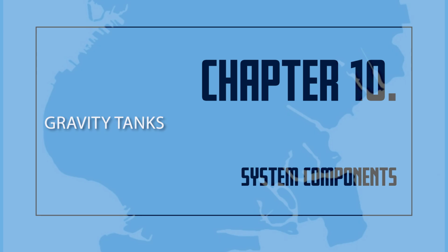Tanks may be located on the tops of buildings or raised on tall supporting towers. The water pressure in a gravity tank system depends on the elevation of the tank. This is the main advantage over other kinds of systems. For every 1 foot the tank is above the discharge outlet, 0.433 pounds per square inch of water pressure is generated. In other words, the higher the tank elevation, the greater the water pressure.